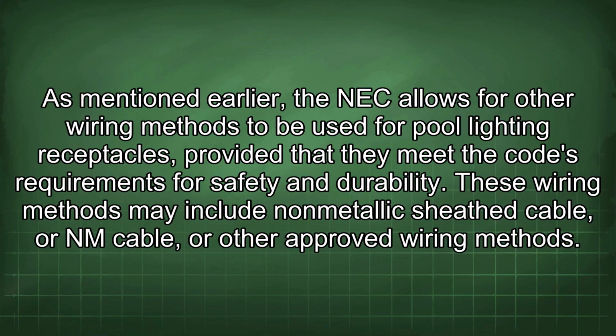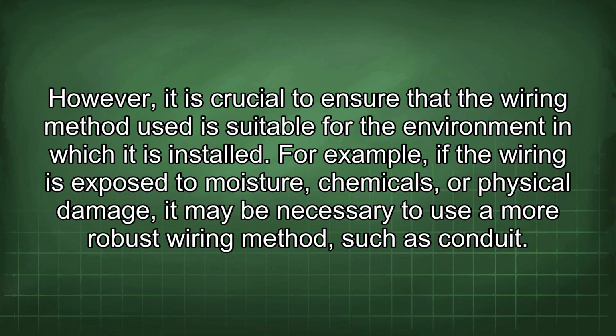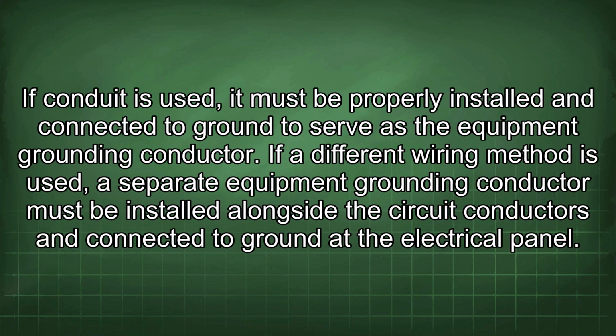These wiring methods may include non-metallic sheath cable, or NM cable, or other approved wiring methods. However, it is crucial to ensure that the wiring method used is suitable for the environment in which it is installed. For example, if the wiring is exposed to moisture, chemicals, or physical damage, it may be necessary to use a more robust wiring method, such as conduit. If conduit is used, it must be properly installed and connected to ground to serve as the equipment grounding conductor. If a different wiring method is used, a separate equipment grounding conductor must be installed alongside the circuit conductors and connected to ground at the electrical panel.